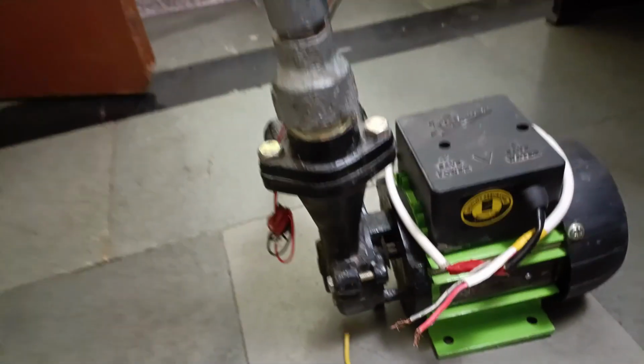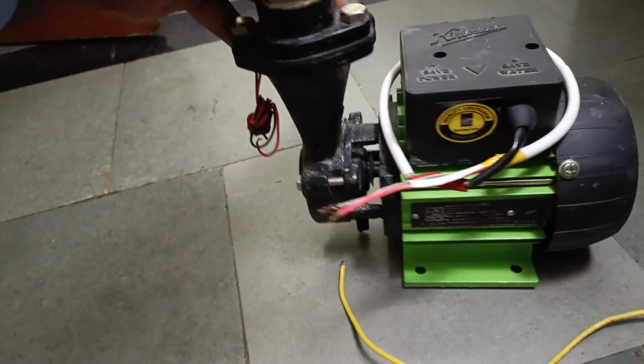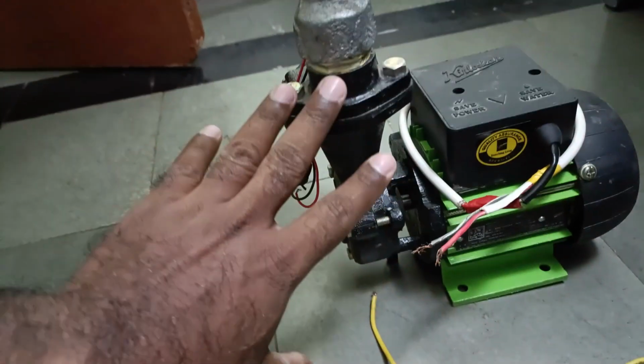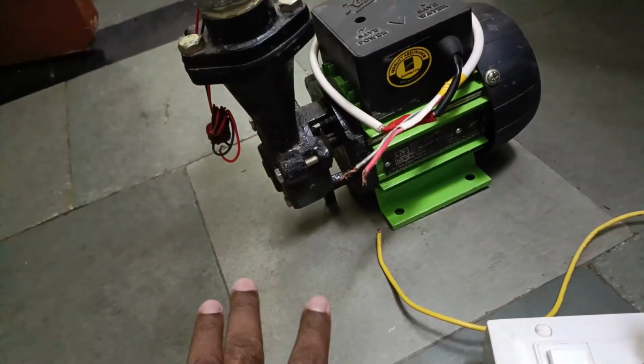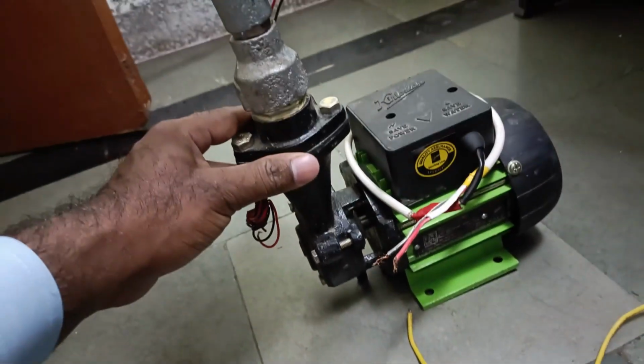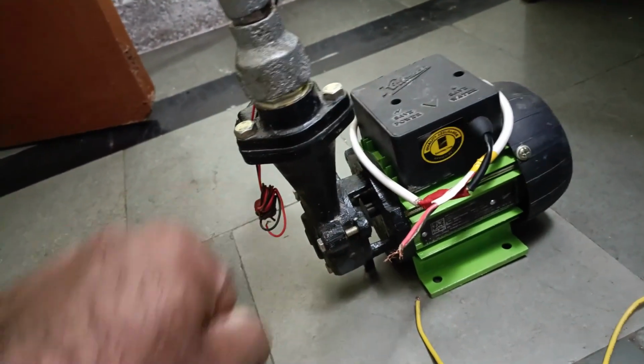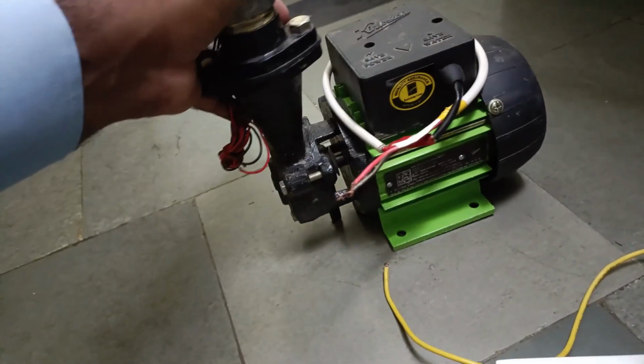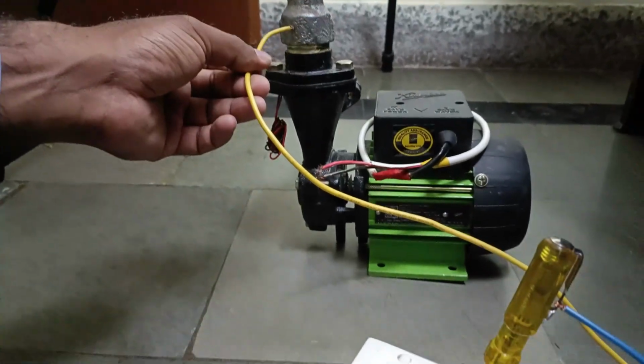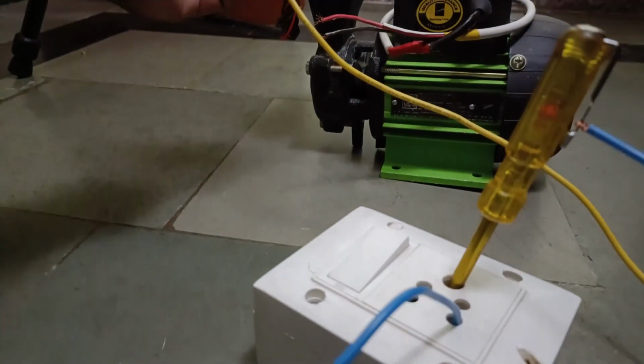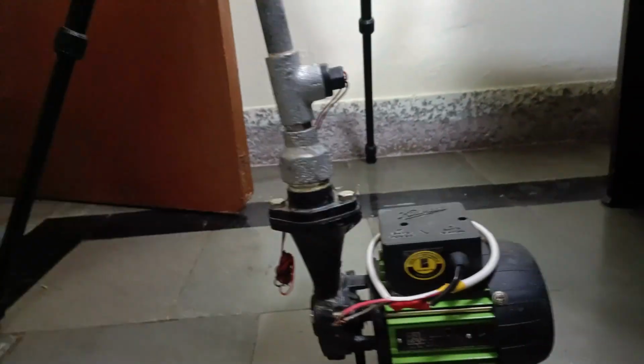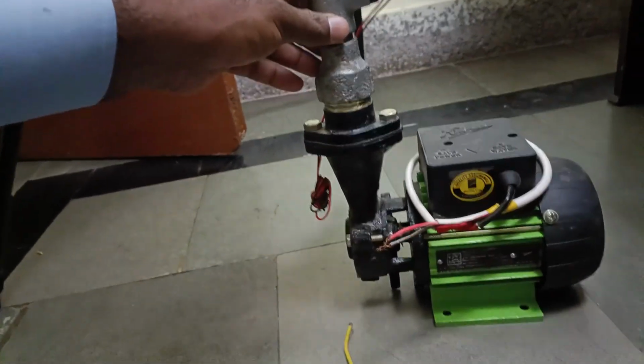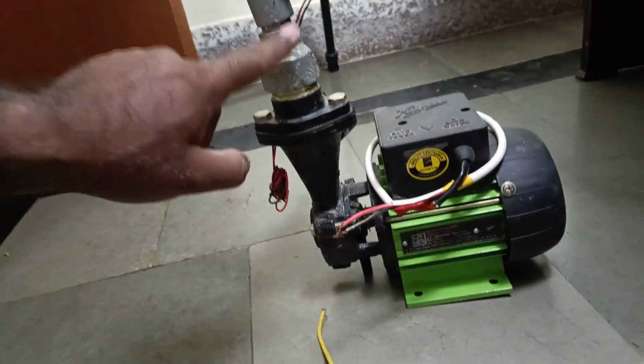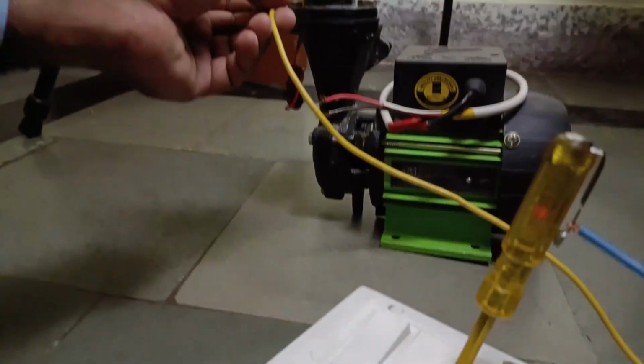But the problem here is that my motor is only touching the ground, that means there is no proper earthing. I have not completely done earthing of this motor, I just kept it on the ground. In this condition, my tester started glowing, which according to them means there is a proper earthing. But can you say that just by putting the motor on the ground, there is proper earthing? No, this does not happen.